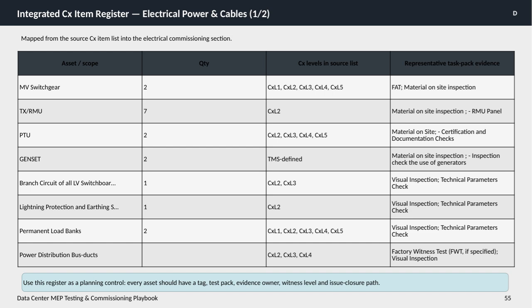On this table, you can see different electrical assets along with their quantities and the corresponding commissioning levels assigned from the source list. For example, MV switchgear requires thorough testing across multiple levels, from CxL1 through CxL5, supported by factory acceptance tests and material inspections on site.